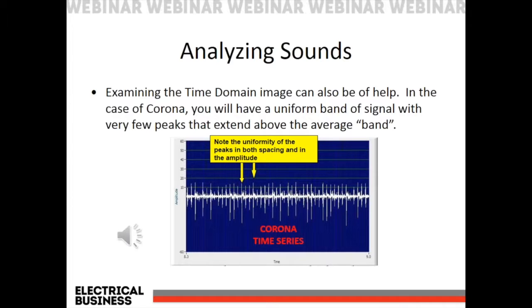So you can see right away that we're using the patterns of the discharges in the time series to determine what we're looking at here. That's important because now we can take this to a diagnosis level, whereas with just listening, we wouldn't know what we're listening to. You can see that we have very evenly spaced discharges. We do have some longer lengths on the bottom part of the amplitude of the spectrum there. That gives us our indication that this is actually corona, and that's important to know. So now we can use this, because there are very few technologies that can detect corona.